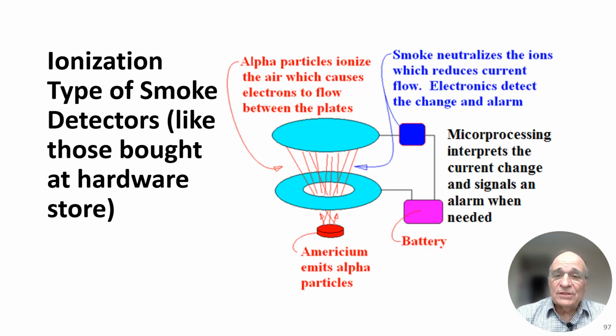Smoke detectors are also used in LNG facilities. This is an ionization type smoke detector. It's the type that you'd buy in a Home Depot. It's relatively inexpensive. It has a radiation source, and alpha particles are transmitted from one point to another point. Those alpha particles ionize the air, which causes electrons to flow between these two plates. As smoke enters this area, it neutralizes the ionization of the air that occurs between these two plates, therefore changing the amount of current that is being fed between these two plates. Microprocessing is used to interpret that, and then it will give a signal to alarm if smoke is entering the area between the two plates.